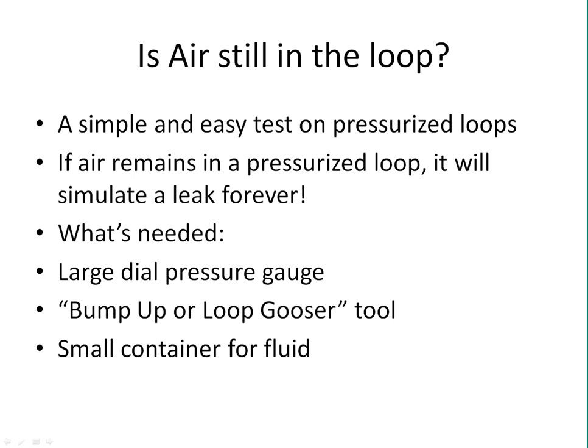Kind of moving along, guys, we're going to talk about, on a pressurized system, what if air is still in the loop? Well, sometimes you have the luxury of actually hearing it. Perhaps that's the reason why the homeowner called you out there, as they heard gurgling or they heard the pump rattling when the air pockets came through it. But there's some easy and simple things you can do to determine if perhaps you still have captive air in that loop. Because I want to remind you that if air remains in a pressurized closed-loop system, it will simulate a leak forever. So what are you going to need?